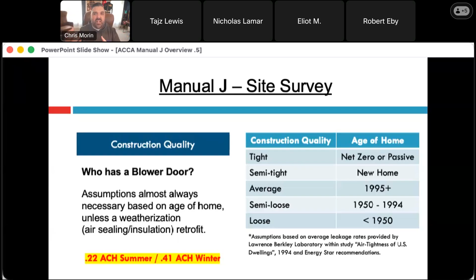I've seen in the Northeast that heat loss and heat gain drastically change by 15 to 25% by air sealing and insulating a home. So just simple weatherization, which is usually covered by a lot of utility programs, will drastically change your loads. So if you're going to be doing that, you need to do the load calc with what the conditions are going to be. And for tight construction, which is typically new homes that are close to net zero, you're talking about meticulous air sealing. All vents have backdraft dampers, and there's no recessed lighting that could create excess leakage.